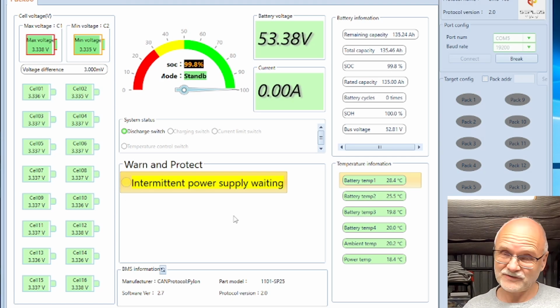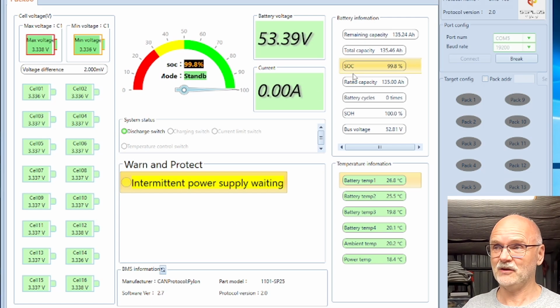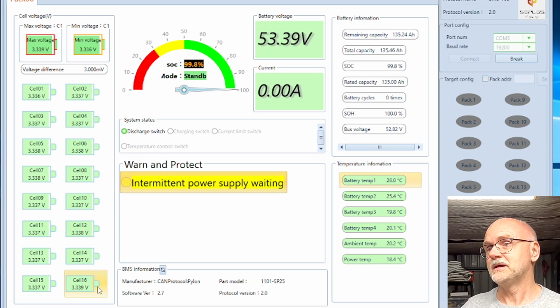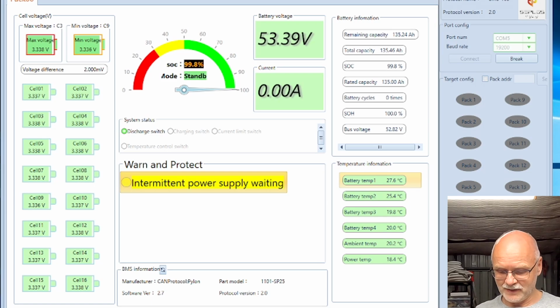Okay guys, so here's the problem. The BMS has turned off charging because it thinks the battery is full. We're at 99.8% state of charge, but this is not true. It was only cell number 16 peaking at 3.65 volts that caused the BMS to turn off. The recovery voltage is 3.6 volts, so everything under that should turn the BMS back on, but it doesn't. As you can see, we have a warning here: intermittent power supply waiting. Great, right? The BMS is working fine.